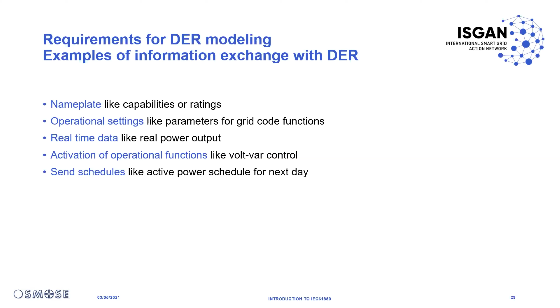We may activate certain operational functions — a DER may support volt-var control, for example, and we may need to activate this support when wanted. If we're just using a DER with active power, we may want to send schedules instead of individual set points to the DER. So this is the kind of information we exchange with a DER, and it's the scope of the data model we build up with 61850.